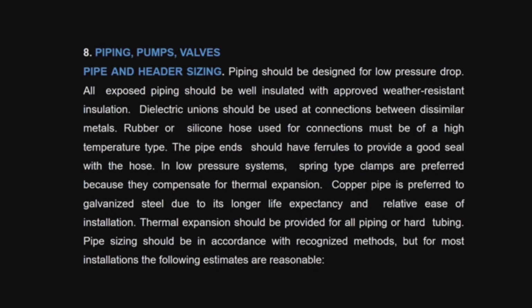Piping, pumps, valves, pipe and header sizing. Piping should be designed for a low pressure drop. All exposed piping should be well insulated with weather resistant insulation. Dielectric unions should be used for connections between dissimilar materials. Rubber and silicone hoses used for connections must be of high temperature type.